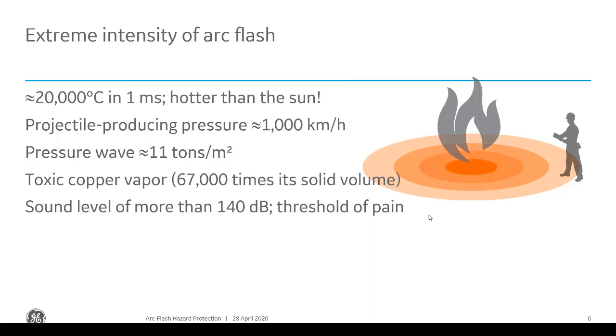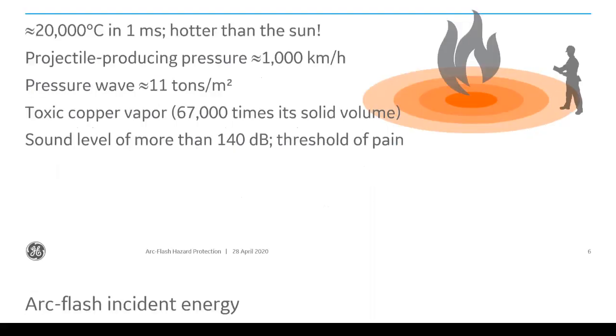Okay. So arc flash can oscillate and escalate if not constrained in a very, very short period of time. We're talking about milliseconds here. As I mentioned, 1 millisecond to get it to its hottest point. And because of that, a single phase fault can engulf and evolve over conductors, evolving to a 3-phase fault for lingering arc flash cases.